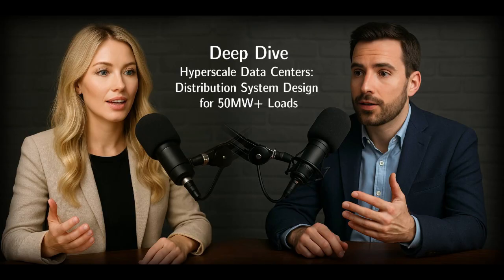Standard distribution might rely on simpler regulators or just the inherent stiffness of the system. For data centers needing that tight plus or minus 2% band, you almost always need sophisticated load tap changing transformers, often abbreviated LTCs, at the substation. Okay, LTC. And maybe supplementary step voltage regulators with advanced electronic controls out on the feeder if it's a lower voltage feed. Switched capacitor banks are crucial for managing reactive power and supporting voltage. And continuous real-time voltage monitoring and automated control systems are pretty much standard. You can't just set it and forget it.